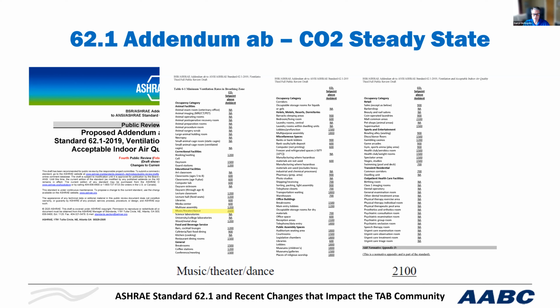So this is an important thing to consider. Another important thing to consider is how the sequence of operation works. I've seen so many sequences of operations that basically state, stop to modulate the outside air damper when it reaches the set point, or 1,000 parts per million. And that is incorrect. Not only is the 1,000 parts per million perhaps incorrect, but modulating once you reach that set point, well, that's a steady state. I mentioned before, it takes a long time to get to steady state, perhaps an hour or more.